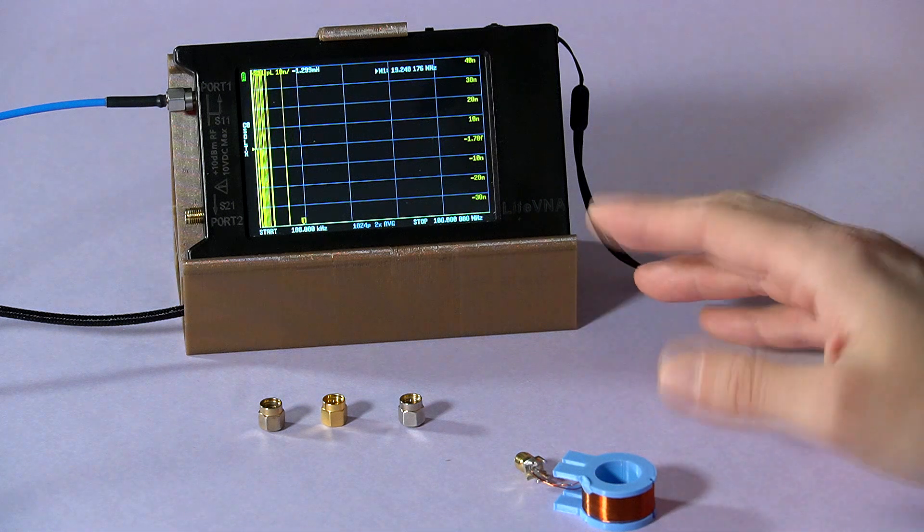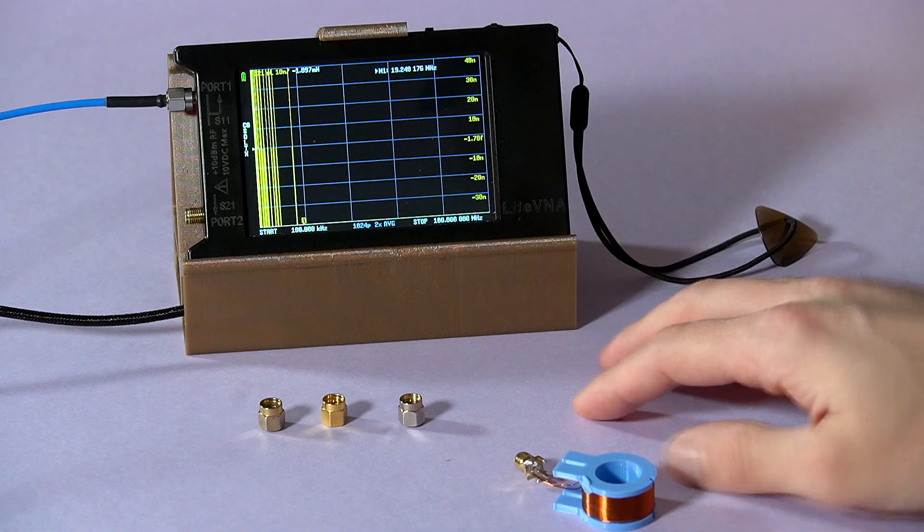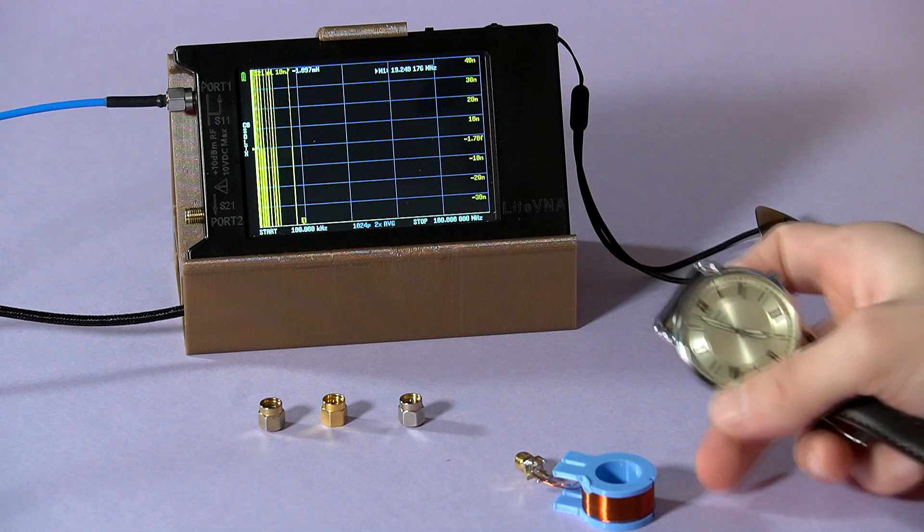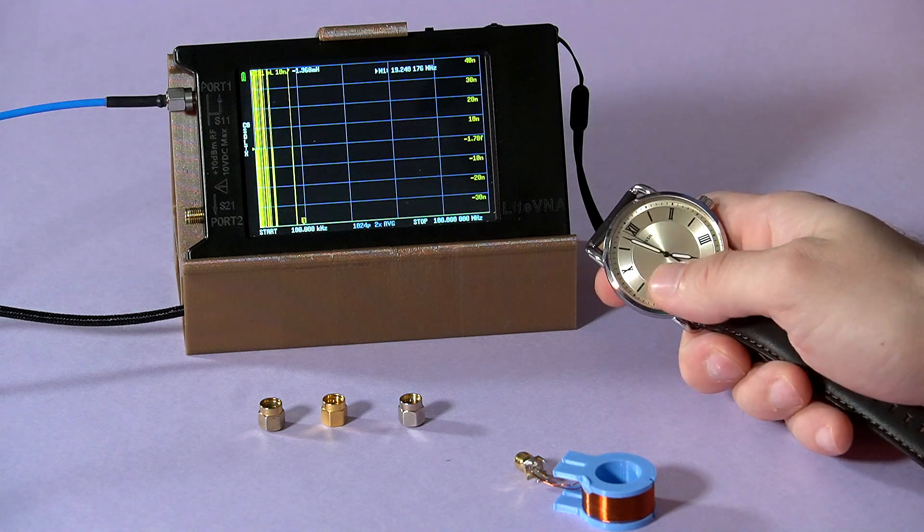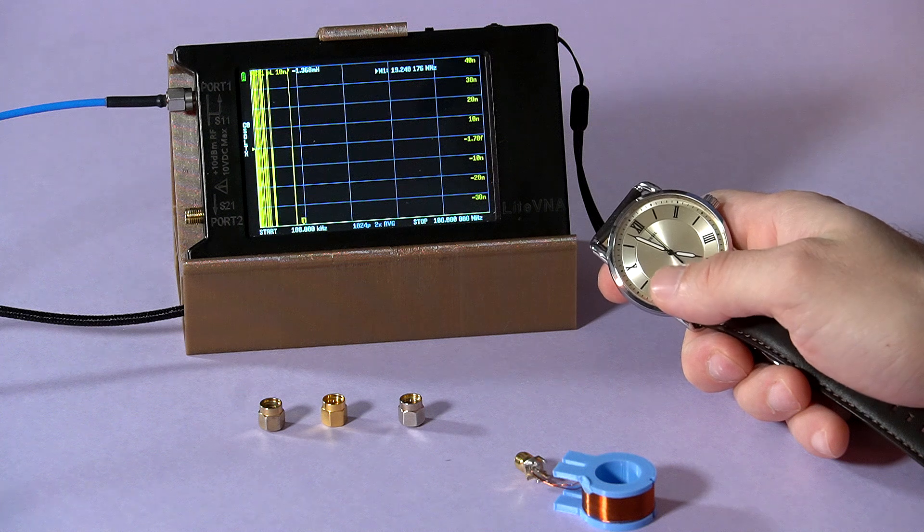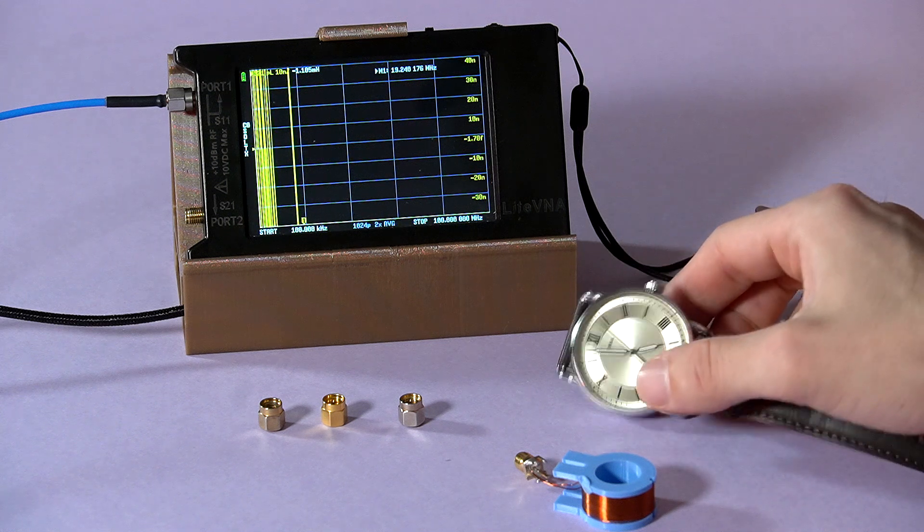So this is not always important of course, if you just want to make a basic measurement, it will not really matter, but when the actual accuracy is critical, it's important to let the measurement equipment stabilize itself before beginning to use. Commonly, 10 to 30 minutes should be sufficient.